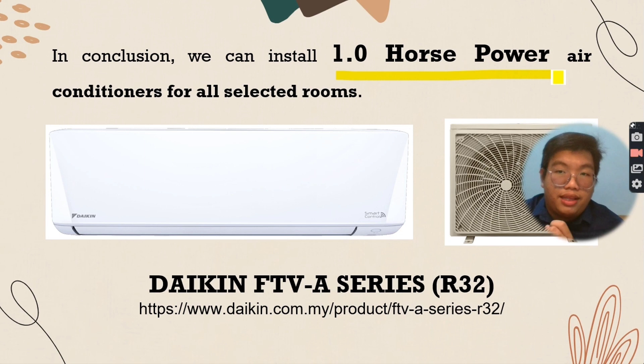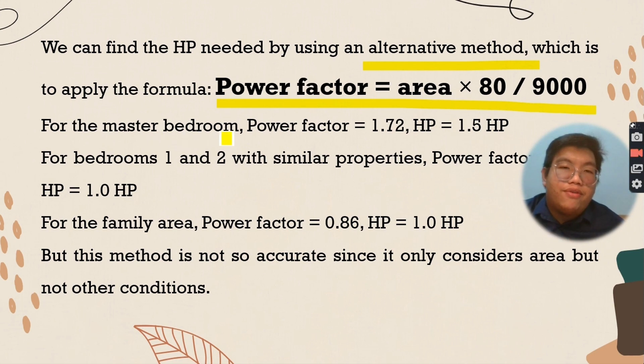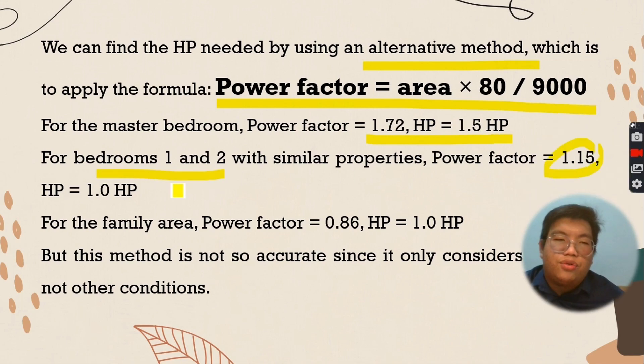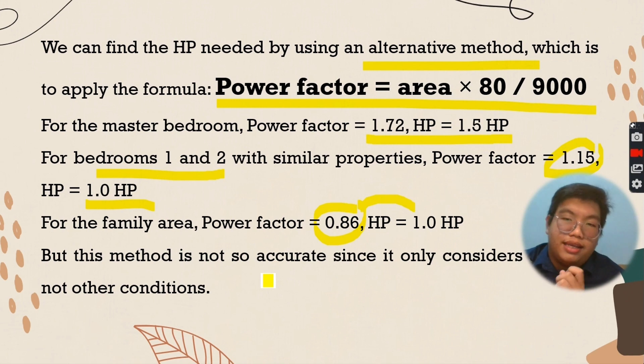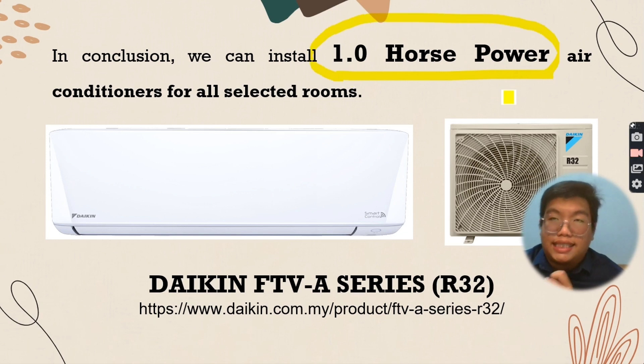We can also determine the horsepower using an alternative method where the power factor equals area times 80 divided by 9,000. For the master bedroom, the power factor is 1.72, adjusted to the nearest 1.5 horsepower. For bedroom 1 and 2, the power factor is 1.15, near to 1 horsepower. For the family area, the power factor is 0.86, so the nearest is 1 horsepower. However, this method is not very accurate as it only considers area. So we apply 1 horsepower for all selected rooms.